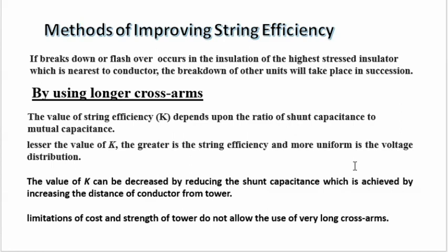By increasing the distance of conductor from the tower, we are actually increasing the dielectric medium or the dielectric strength of air, which is actually present between conductor and tower. But this method has some limitations, and the limitation of cost and strength of tower do not allow the use of long cross arms.